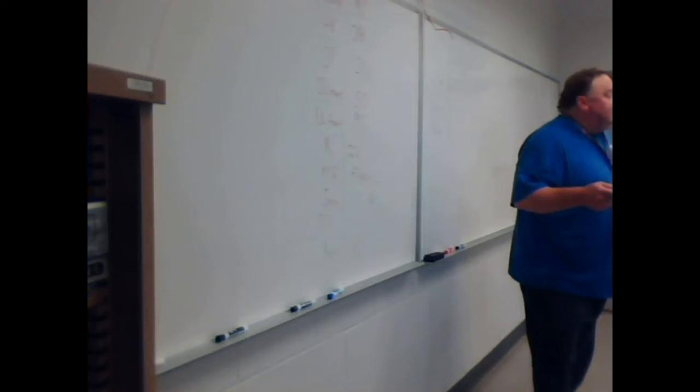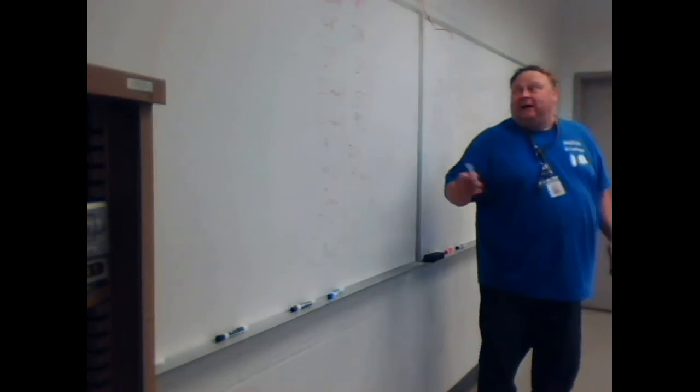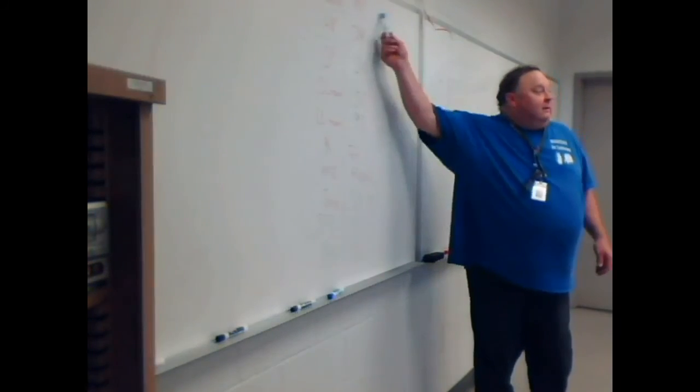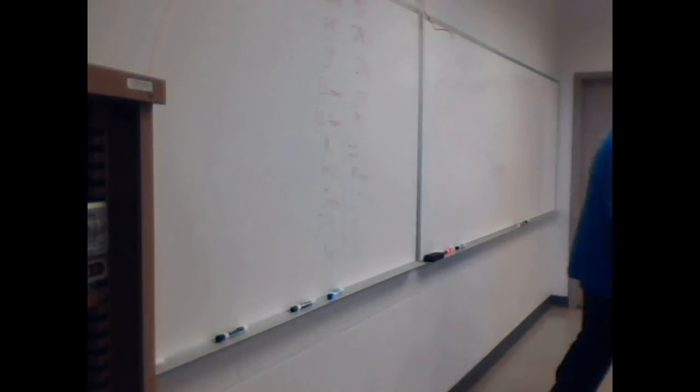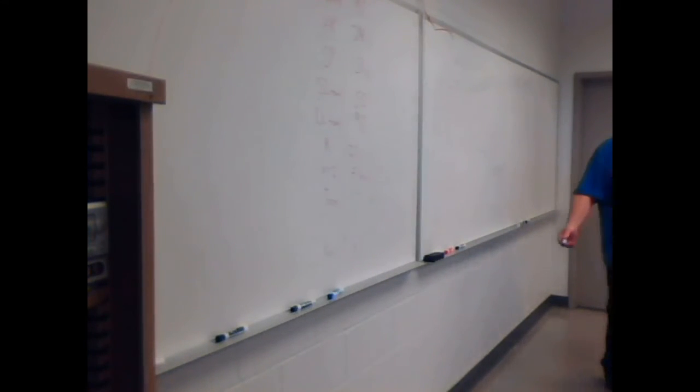Now, this was outside. What's the temperature outside? 95. So it couldn't cool anymore. It might have cooled more, but it can't, right? It's the same temperature as the ambient. When's the only time we don't have heat transfer? When there's no temperature difference. And so, although that may not be high, it couldn't subcool anymore. If it was 80 outside, it might have subcooled even more. So it's doing all it can do.